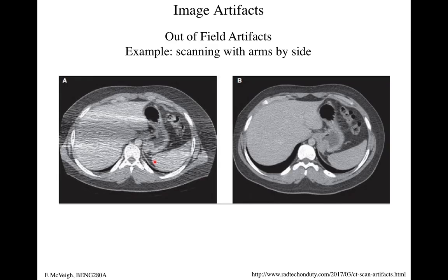So they're out here, and not only are they outside the field of view in terms of sampling, you can see them on the detector in those projections, but when you're orthogonal to them, the fan beam is coming through here, they're not observed at all. So they just come and go in the data. In certain views they appear, and then as the thing's rotating, they just disappear, right?